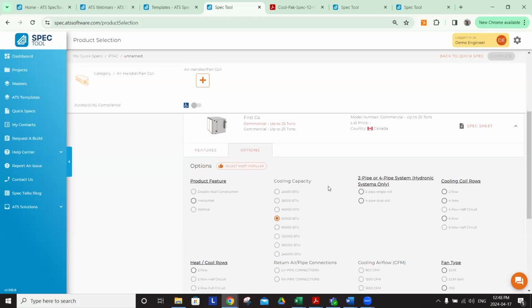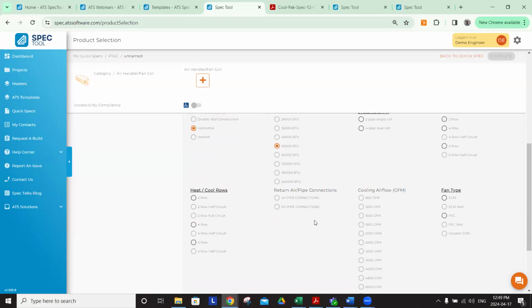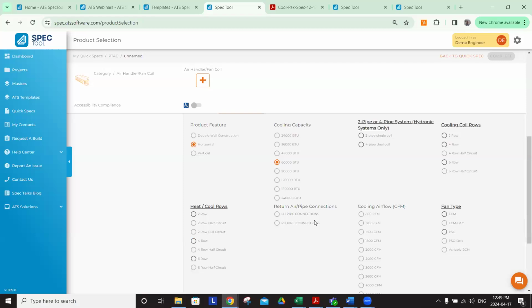And you would know based on your design whether you need a horizontal unit or a vertical unit, especially with a unit that can be very large. If this unit's going in the ceiling above a party room, then we're going to go horizontal, right? But if it's sitting in a mechanical room, then we may be using a vertical. So you can choose, yep, horizontal, very common. Scroll down a bit. Fan type is an easy one. Pretty much anything we want to be putting in these days is ECM, everyone's got their exceptions, but we can choose ECM.